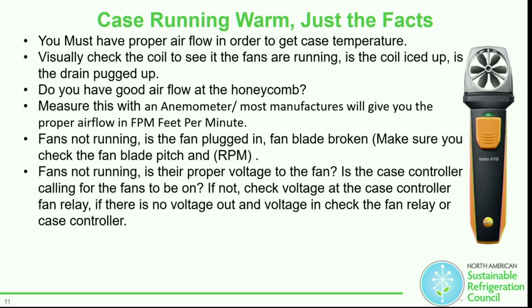So if you have a case that's continually frosting up or icing up in the bottom of the pan, just because it was on when you started the defrost doesn't mean it's going to be on within 5 minutes. So periodically check to make sure there's nothing in the program that's not actually kicking on that fan relay.